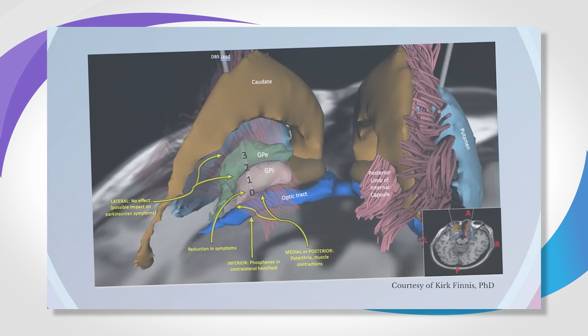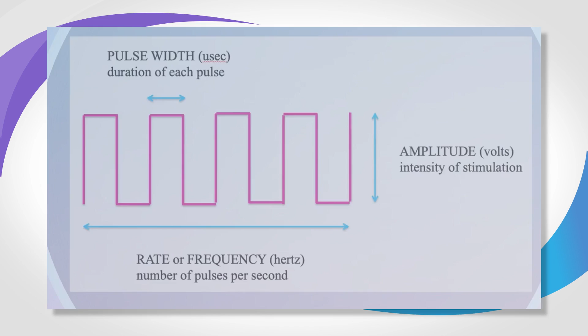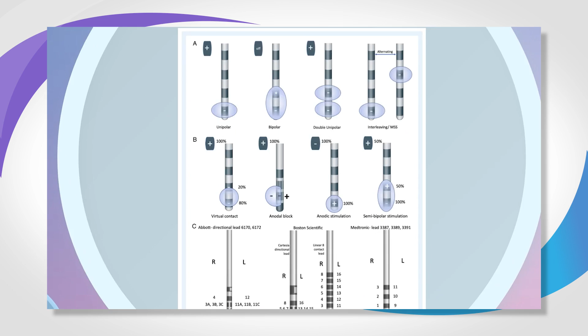There are 4 different parameters that we can change when we're programming. We can change the amplitude, or the intensity of stimulation that we're delivering per pulse. The number of pulses per second, in hertz, is the rate or frequency. Then we can change the duration of each pulse, or the pulse width, which is measured in microseconds. The 4th thing that we can change is the electrode configuration.